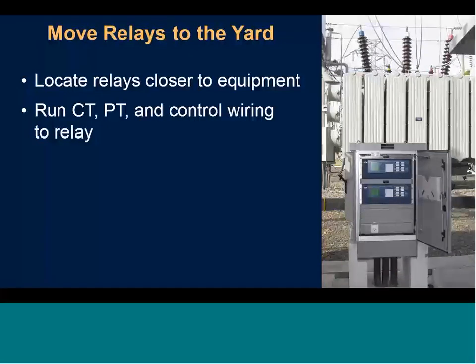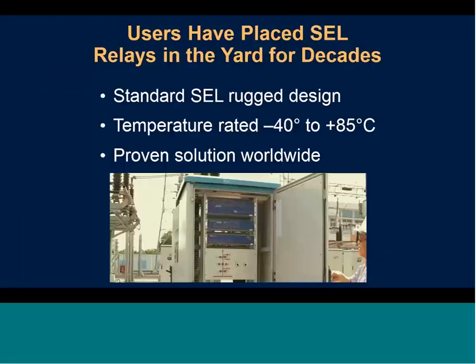The first one we always like to talk about is simply moving the relays out into the yard. You can put them near the equipment and run all of your connections to that device, then have a communications link back to the control house so we can collect SCADA data or any other communications with the relay that we need. You can use DNP protocol, 61850 protocol, whatever is built into the relay.